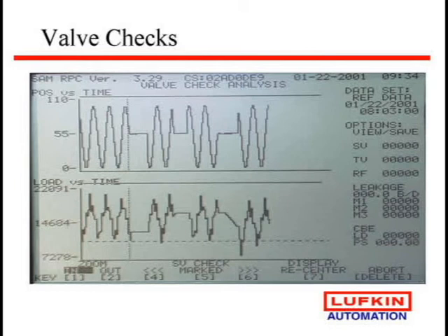And let's just see, is that pump leaking and how much is it leaking before we need to decide we should pull the well? Well, once it hits 100% run time, you better think about pulling the well because you're leaving fluid.